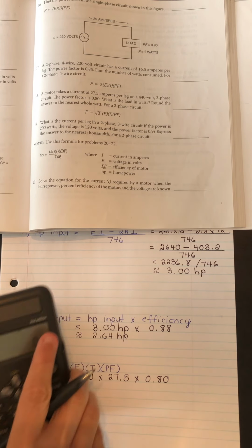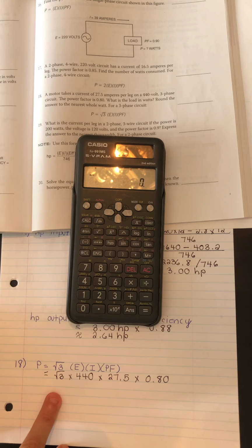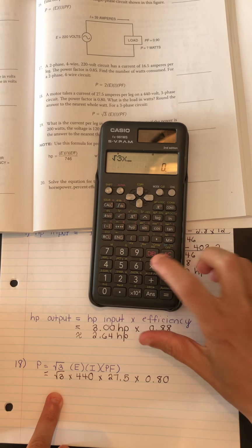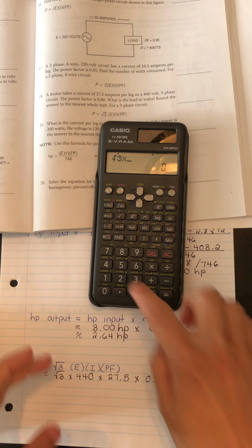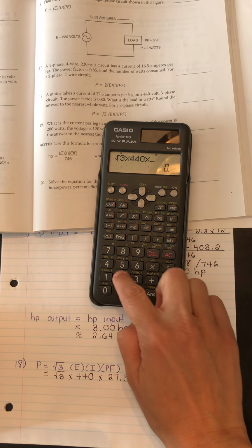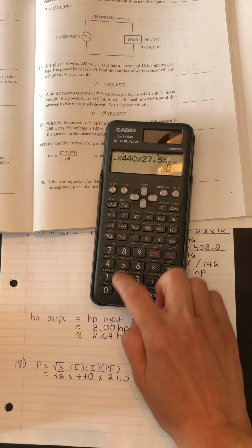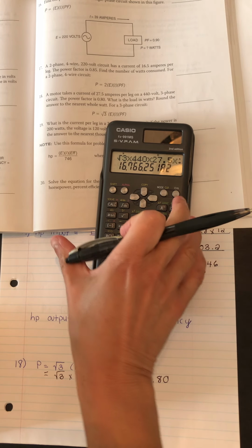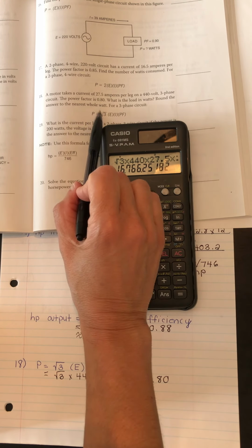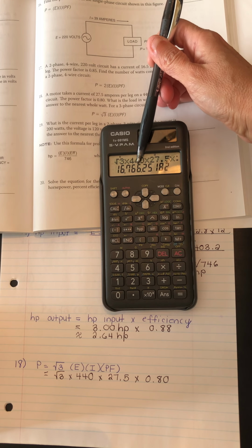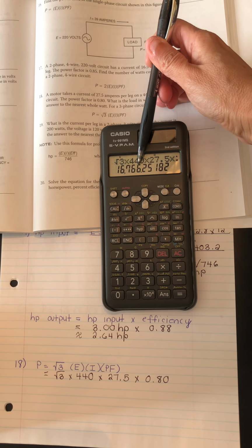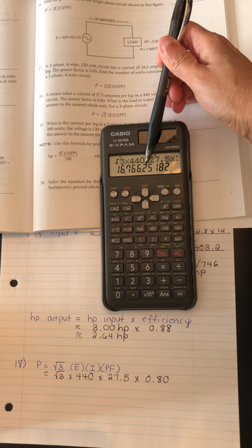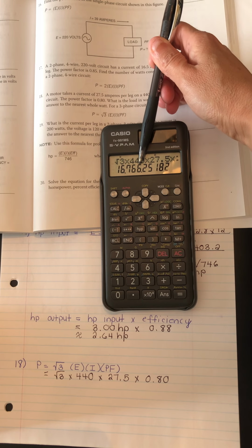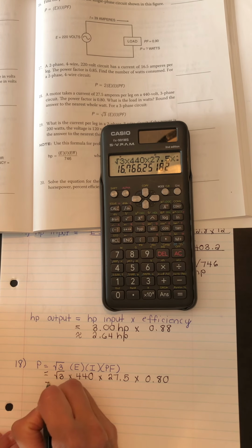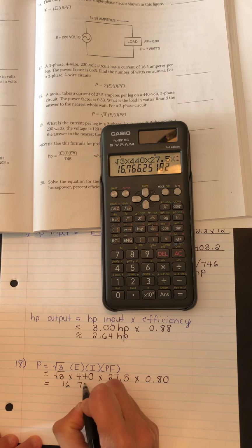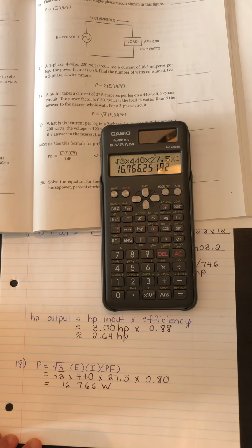So I'll find some place to put the calculator to show you that, okay? The multiplication here, so square root 3 multiplied by 440 and 27.5 and 0.8. And that's the answer there. They're saying round to the nearest whole watt. So round to the nearest one. That would be the position here of the six. The two beside it is not five or more, so this will remain a six. So we end up with 16,766 watts in problem 18.